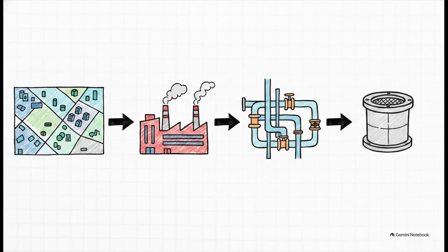Navigating 15,000 individual files means you need an incredibly intelligent numbering system. You can't just use written names because one technician's drain valve is another engineer's discharge valve. Consider a specific tag like N02-FC-003. This isn't random. It tells us precisely what and where this component is. North Unit 2, Fuel Oil Service Pump System, Strainer 003.